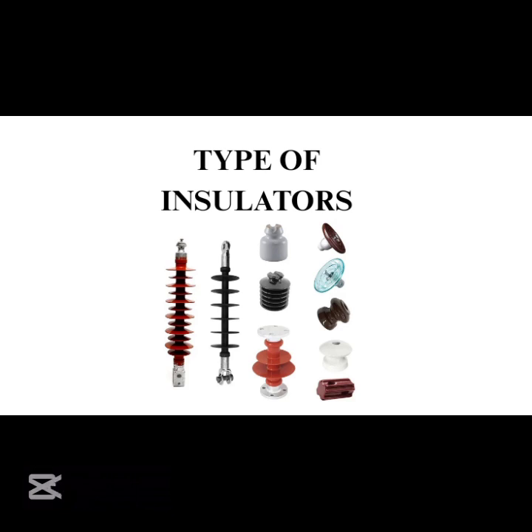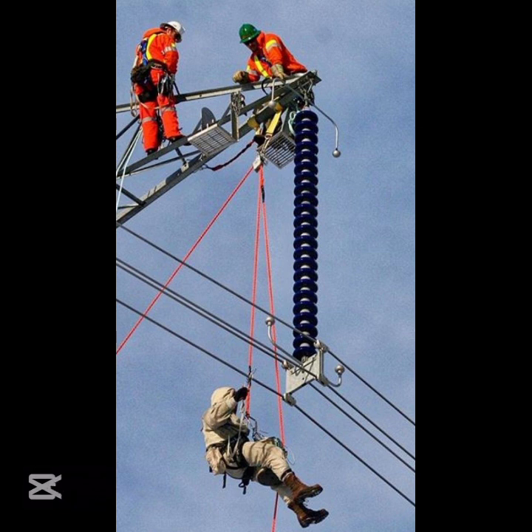This involves selecting insulation materials and levels that can withstand the expected voltage surges caused by lightning or other electrical disturbances. Proper insulation coordination ensures that the electrical system can handle transient overvoltages without failing. It involves careful planning and selection of insulation materials based on the system's voltage levels and expected surge conditions.